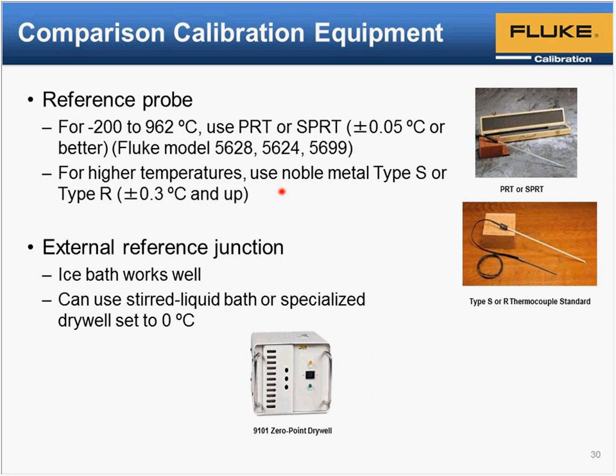One more component for the thermal calibration system is how you handle the reference junction. We've already talked about how to have the readout handle it for you, but typically the uncertainties are a little bit bigger. Here's an option if you don't want to be bothered with making an ice bath: you use a basic ice bath simulation furnace like this one, where its job is to just stay at 0 degrees C, with some wells where you can insert the thermocouple reference junctions.